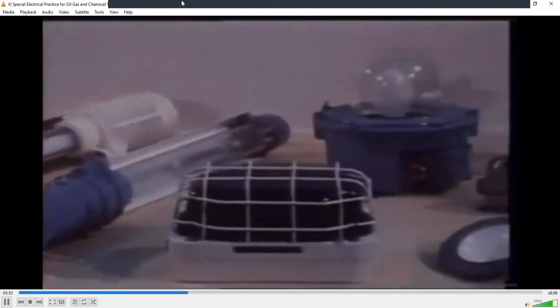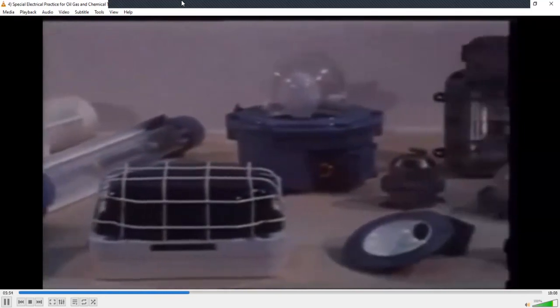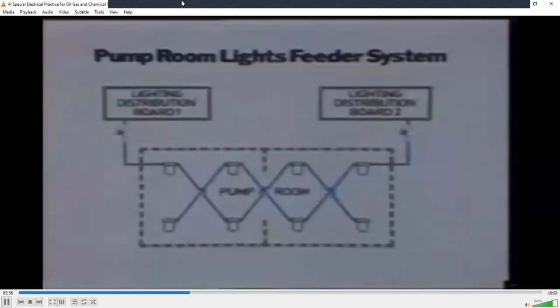Light fittings in hazardous areas must be of flame-proof or pressurized types. These light units must be on at least 2 independent final branch circuits, so that one may be disconnected for maintenance, while the other supplies enough light for safe access. Switches for these lights must be double pole, interrupting both supply lines, and must be situated outside the hazardous area.